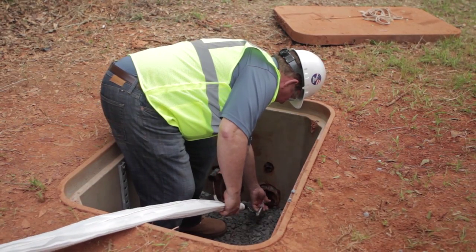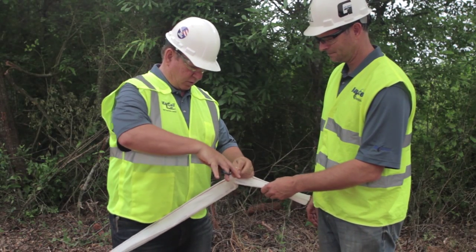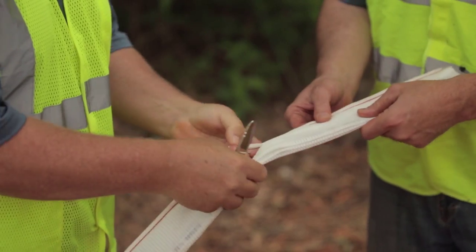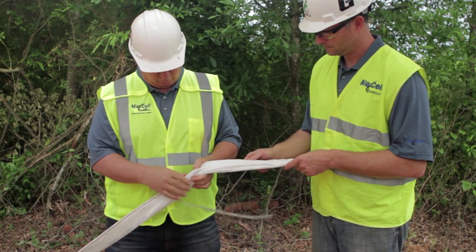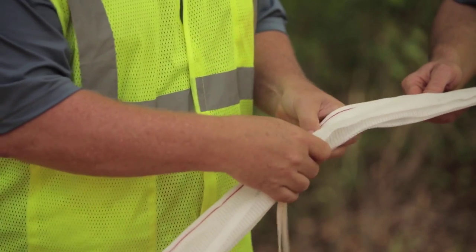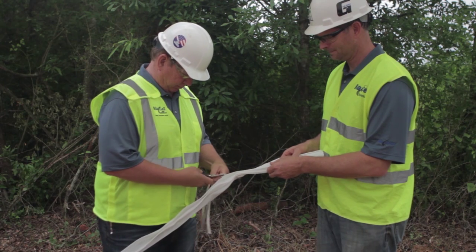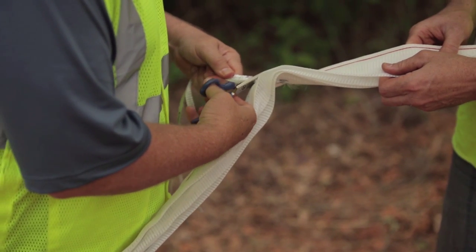This is our recommended technique to prepare MaxCell for pulling into your conduit structure. First, cut a 2-3 inch slit just below the sewn seam, 12-18 inches from the end. Next, pull out 12-18 inches of the pull tapes from the end of the MaxCell through the slit and cut them off. This will allow the pull tapes to float behind your pulling grip when pulling in MaxCell.